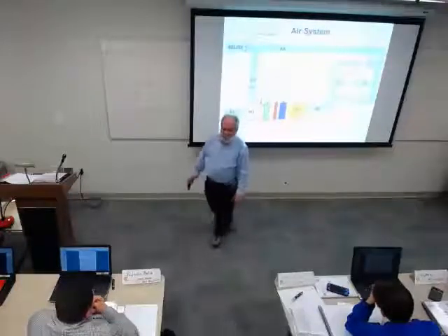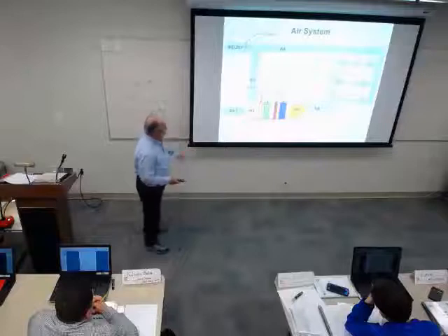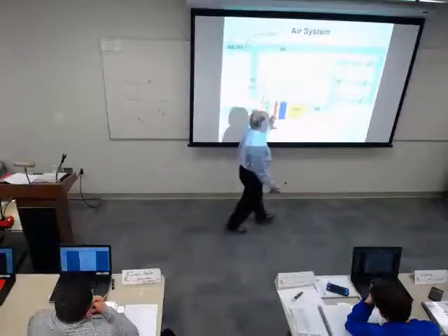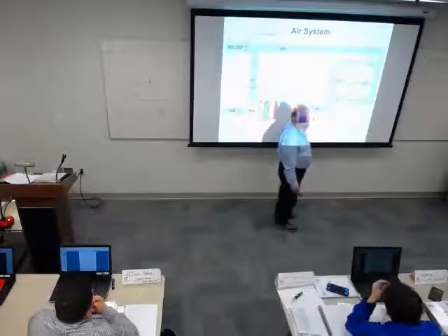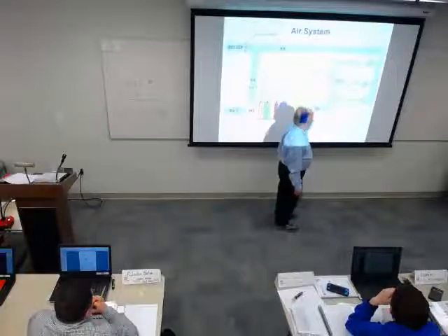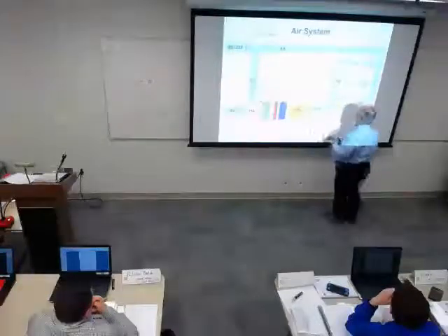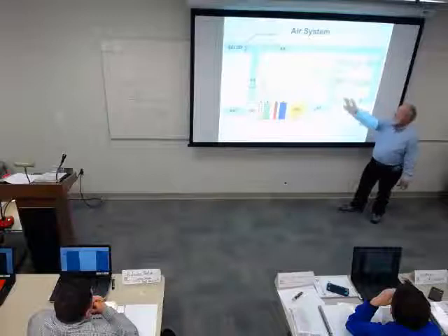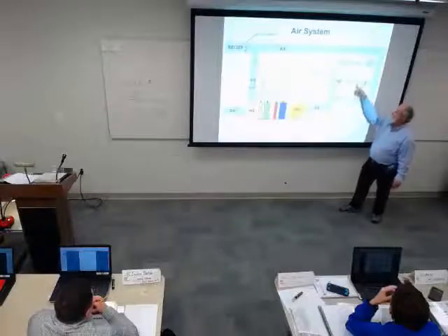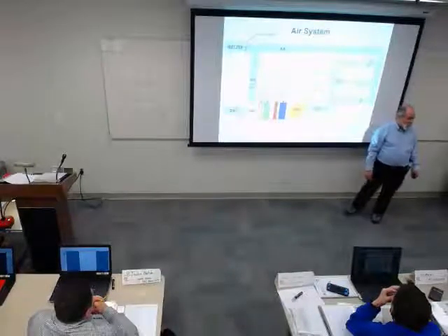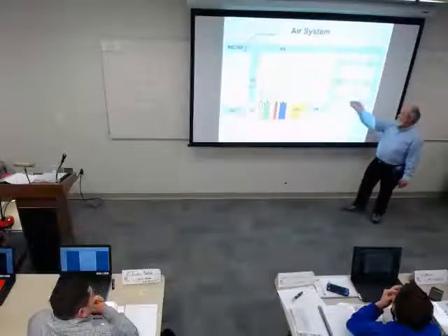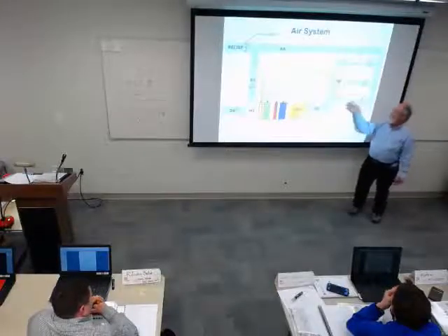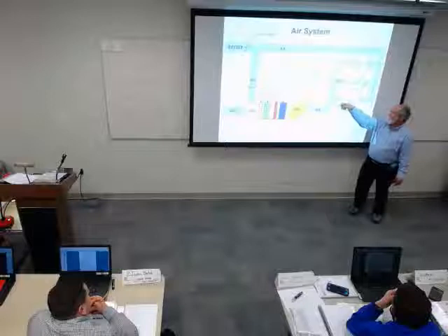So anyway, we come through here, we come through the fan. Since this is a VAV system, the fan speed is going to vary. What happens is the air coming out of here is supposed to be all the same temperature. It goes to things we call VAV terminals or VAV boxes. These get their instructions on how much air to dump into the room. See, this is a damper there.